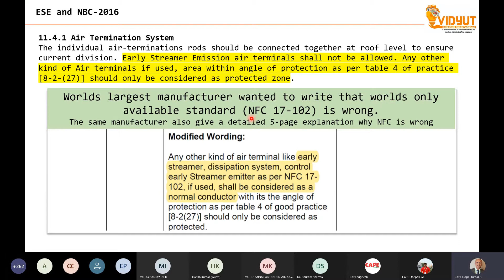So what did the committee do? The committee said, okay, accept his wording and remove the standard which he has put. So the committee accepted the recommendation from this world's largest ESE manufacturer, and put in - look at the wording, the wording itself came from the recommendation of the ESE manufacturer - any other kind of air terminal like dissipation system, ESE air terminal, CSE air terminal shall not be acceptable. So with one word, the whole problem is gone.